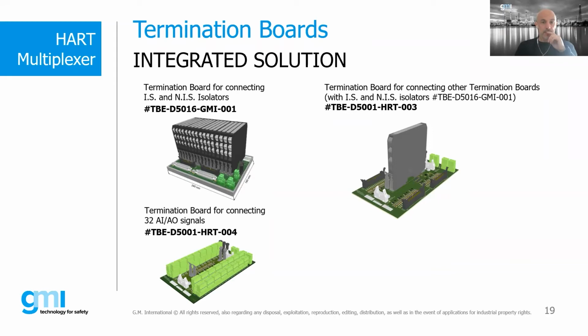On the top right, you have the multiplexer, which is connected to a termination board. The HART is connected to another termination board with some connectors, and those connectors are used to integrate the isolators with other termination boards. In this case, you want to isolate because maybe there are IS signals, hazardous area signals, or maybe you want to isolate to keep away any ground loop effects. Those isolators are connected to this termination board, which via cable is connected to the termination boards on the right. So this is basically the solution we have.